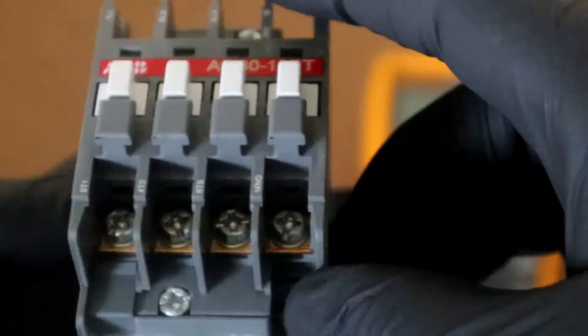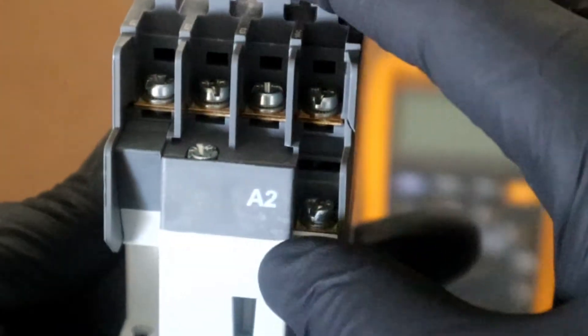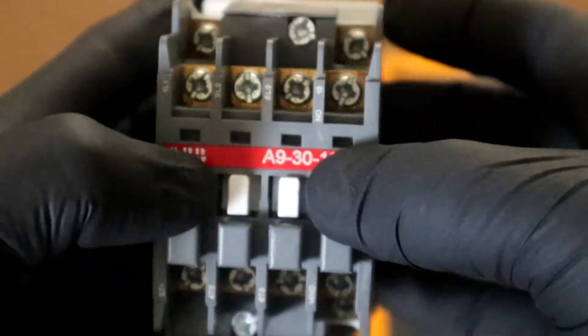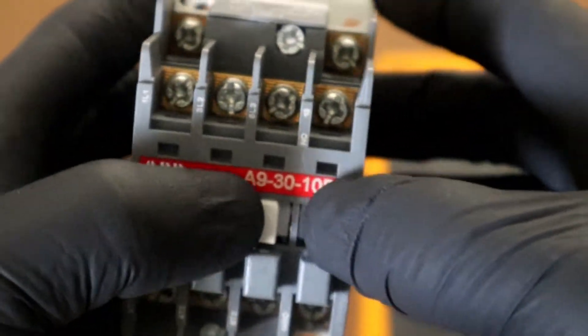This can be checked during a visual inspection. We will have to remove the top cover of our contactor to visually inspect our spring. Our contact points can also become corroded due to carbon buildup, arcing and the list goes on.